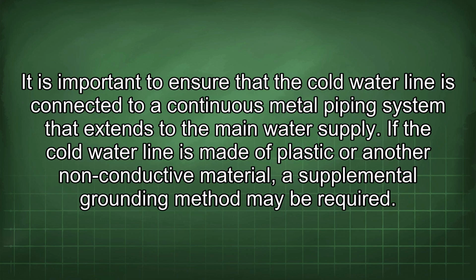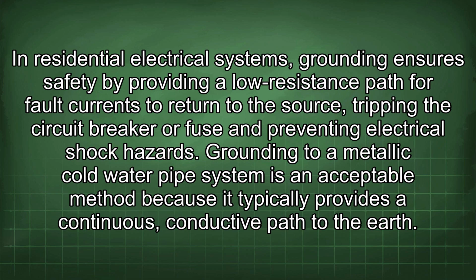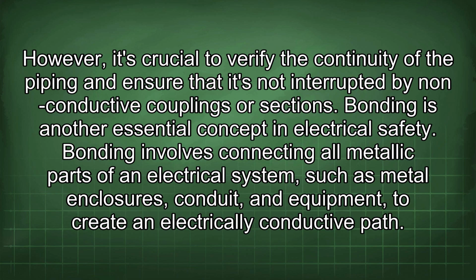It is important to ensure that the cold water line is connected to a continuous metal piping system that extends to the main water supply. If the cold water line is made of plastic or another non-conductive material, a supplemental grounding method may be required. In residential electrical systems, grounding ensures safety by providing a low-resistance path for fault currents to return to the source, tripping the circuit breaker or fuse and preventing electrical shock hazards. Grounding to a metallic cold water pipe system is an acceptable method because it typically provides a continuous, conductive path to the earth.